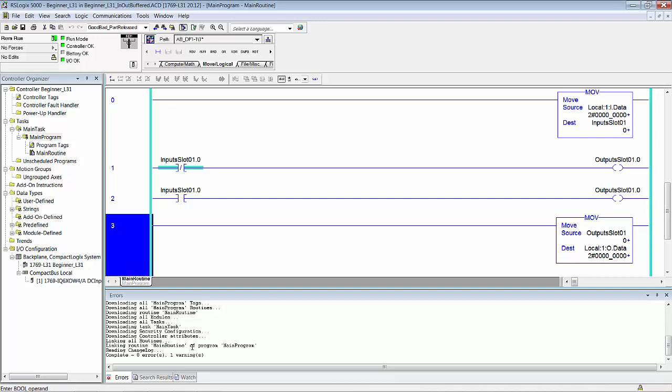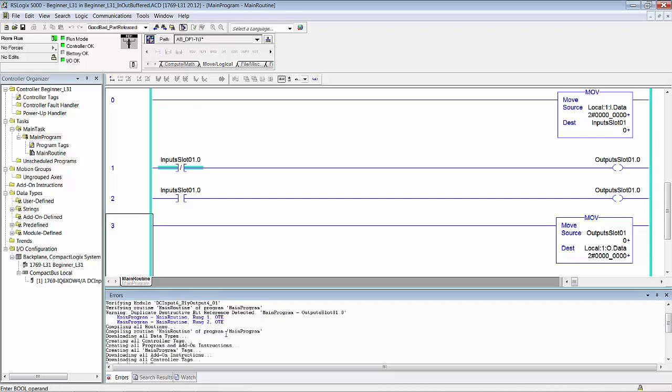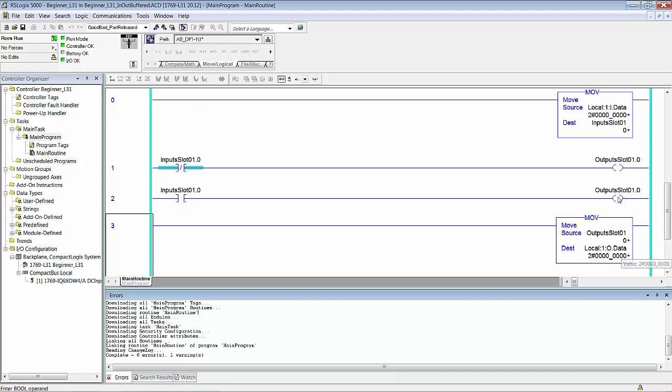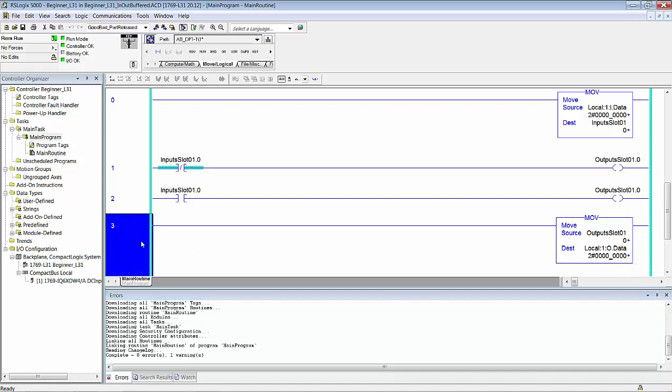By the way, we do have the warning. We'll go down here and scroll up. It's the same thing: duplicate destructive bit reference detected, main program outputs, blah blah blah. These two OTEs. It does occur to me why we do see this flicker on once in a while. It is not flickering at the actual output. So the actual output itself is not flickering on. Let's say we wanted to capture that to see if this actually was turning—even though we see this turning on, is that bit turning on, bit zero of the output data. How would you trap that?